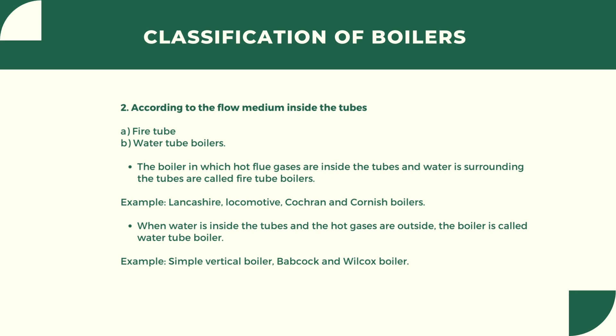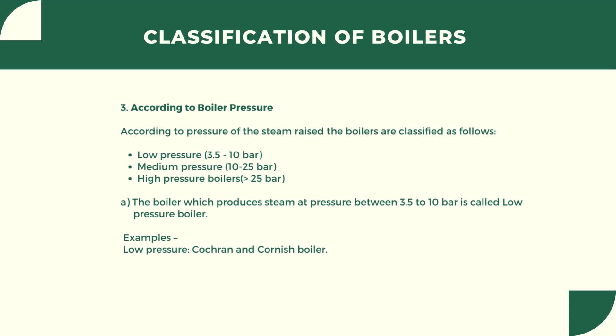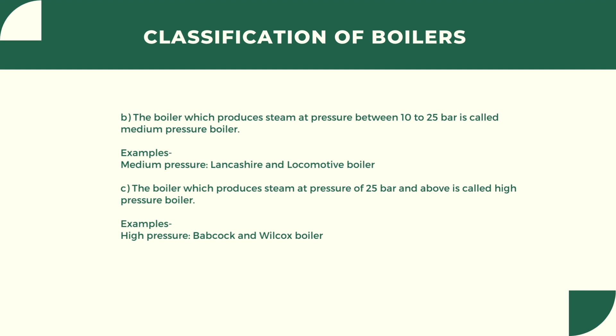Now, according to boiler pressure, boilers can be classified into three categories: low pressure boiler, medium pressure boiler and high pressure boiler. Individually, let us see what is a low pressure boiler. The boiler which produces steam at pressure between 3.5 to 10 bar is called a low pressure boiler. Examples: Cochran boiler and Cornish boiler. The boiler which produces steam at pressure between 10 to 25 bar is called a medium pressure boiler. Medium pressure boiler examples are Lancashire boiler and locomotive boiler. And the third, high pressure boiler: the boiler which produces steam at pressure of 25 bar and above is called a high pressure boiler. High pressure boiler example is Babcock and Wilcox boiler.